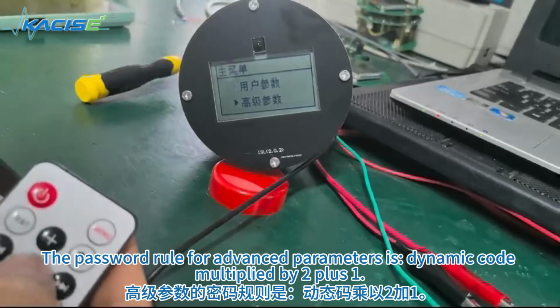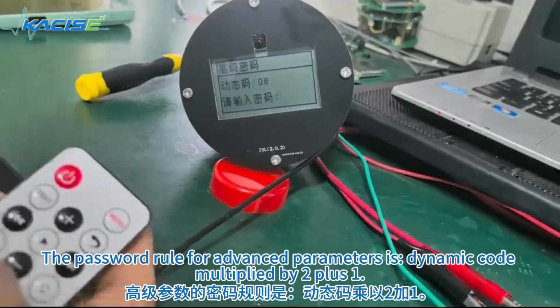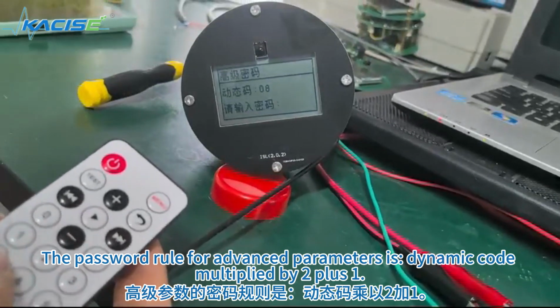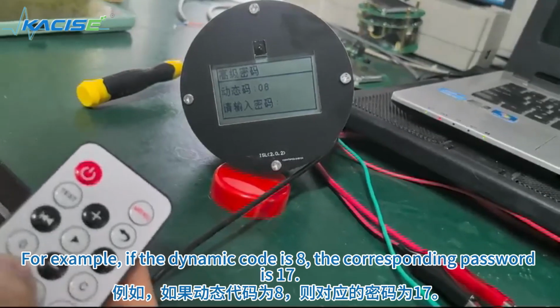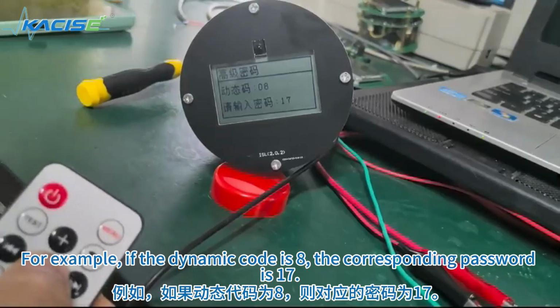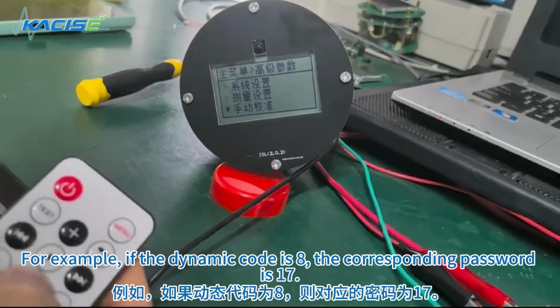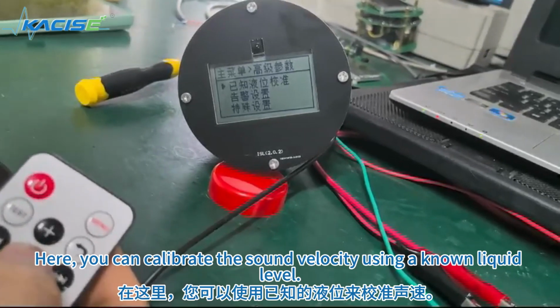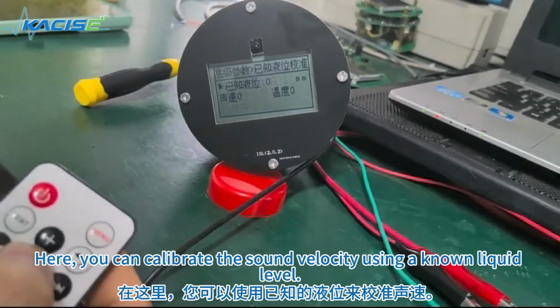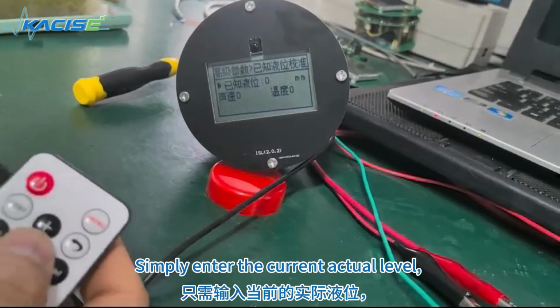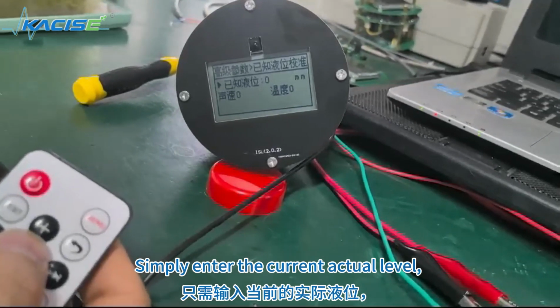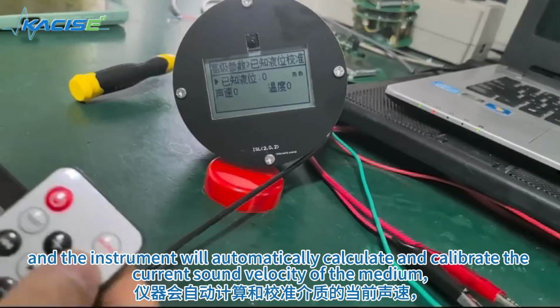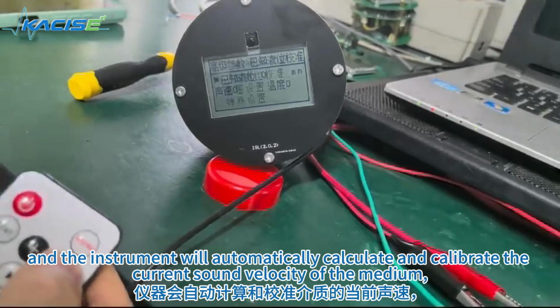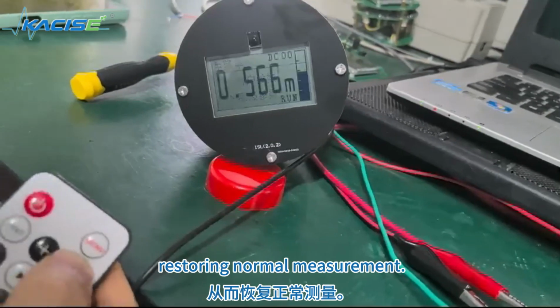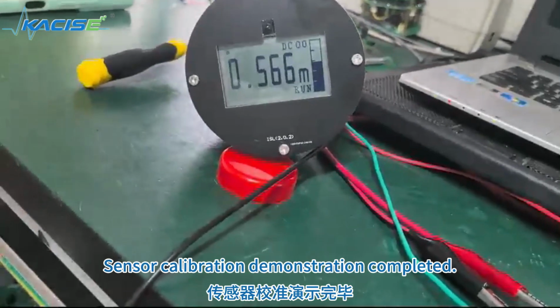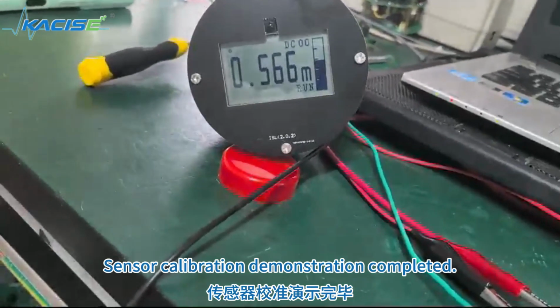The password rule for advanced parameters is dynamic code multiplied by 2 plus 1. For example, if the dynamic code is 8, the corresponding password is 17. Here, you can calibrate the sound velocity using a known liquid level. Simply enter the current actual level, and the instrument will automatically calculate and calibrate the current sound velocity of the medium, restoring normal measurement. Sensor calibration demonstration completed.